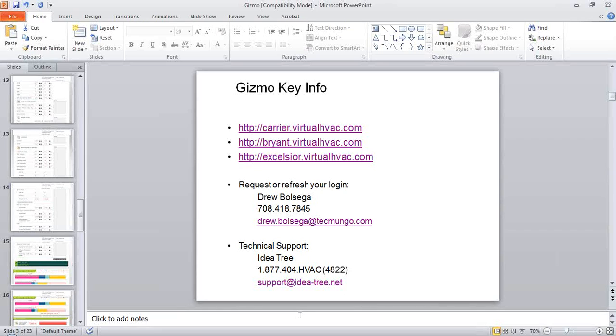All right, so the first thing is that if a furnace is rated 95% AFUE, it's 95% AFUE. That already takes into account the single versus two-stage versus modulating gas. So those AFUE formulas are already taking that into account. AFUE is annual fuel utilization efficiency. It is not a straight combustion or thermal efficiency number. It is already a biased calculation that takes into account cycling losses. So there are more cycling losses with a one-stage than there are with a two-stage than there are with a modulating or three-stage unit. So the AFUE number already takes that into account.